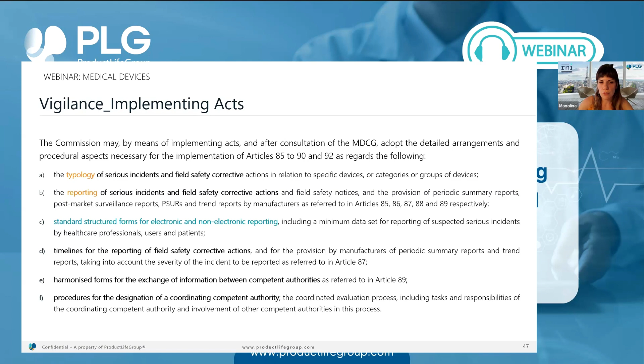And now, about the electronic system and vigilance. As you know, EUDAMED is going to be constructed of 6 modules. The vigilance module is about vigilance and post-market surveillance, where the reporting of adverse events and post-market surveillance information can be done through this portal. But it is not fully functional yet, so the obligations and requirements related to this module will become applicable 6 months after the publication of the notice in the Official Journal of the European Union.